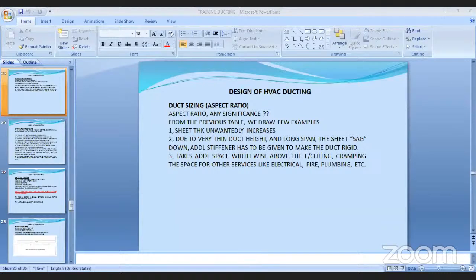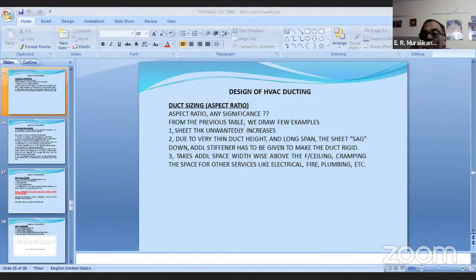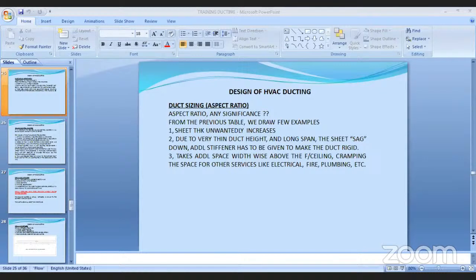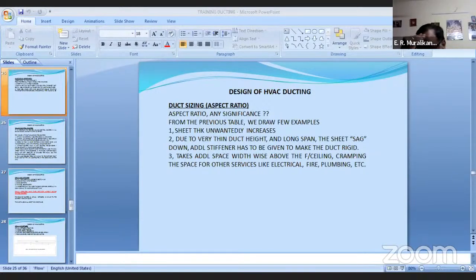What is the best duct material required to cool one TR of cooling? Repeat once again. What is the best duct material required to cool one TR of cooling? See, for duct material you can have FRP, PIR ducts, GI ducts or MS ducts. It suits whatever the client specifications or tender specifications. It's not that we should go for one particular material.